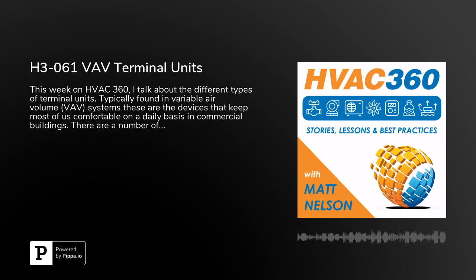So, supplemental heating around the perimeter, or if you have a roof condition, that's where you're going to use it. Typically, if you're going to use a single VAV box, you're going to have it cooling only. That's going to be someplace that always needs cooling, doesn't really ever need heating, and you don't have to worry about a minimum there. Or you have a shutoff box, whichever is specified. When you're dealing with these single zone boxes, that's one of the things that even I wrestle with. Obviously, with ASHRAE 62.1, they say if it's an occupied room, you're going to have a minimum ventilation rate. I've had cases where the room isn't as highly occupied as you would have imagined, and you do get some subcooling, which obviously causes problems. Thermal comfort really kind of trumps the need for outside air, because if you can't be in a space to actually use it, then it's pointless to have good indoor air quality.